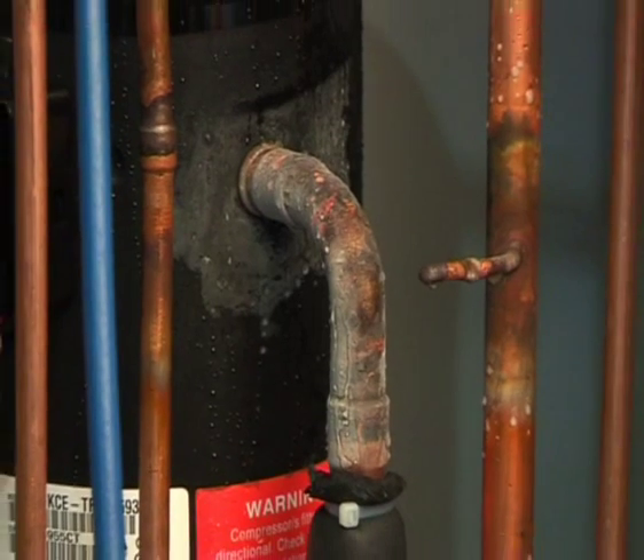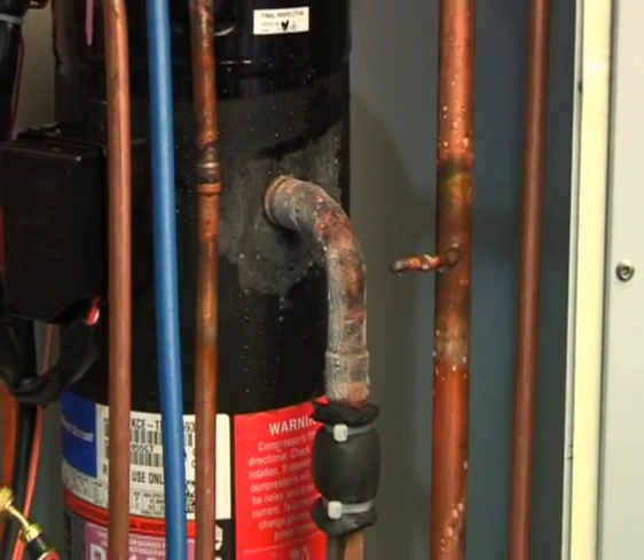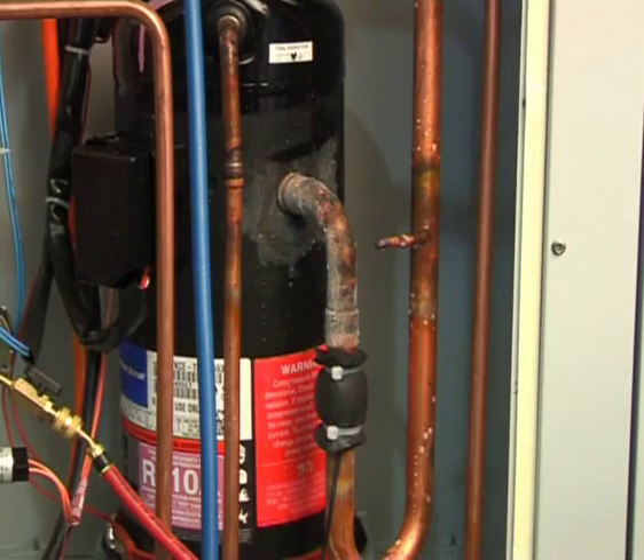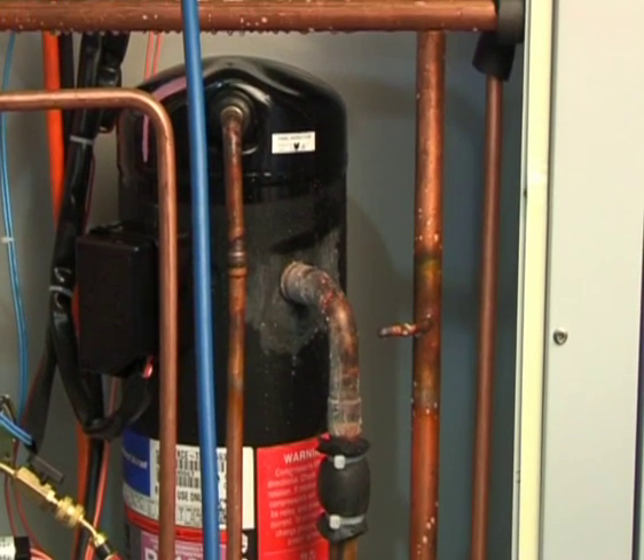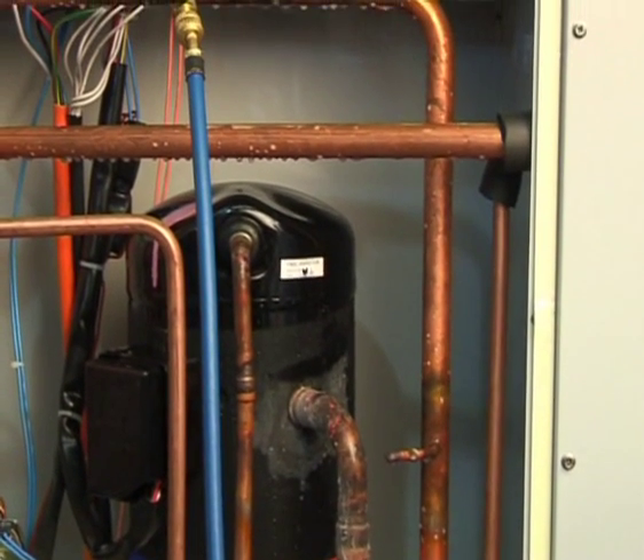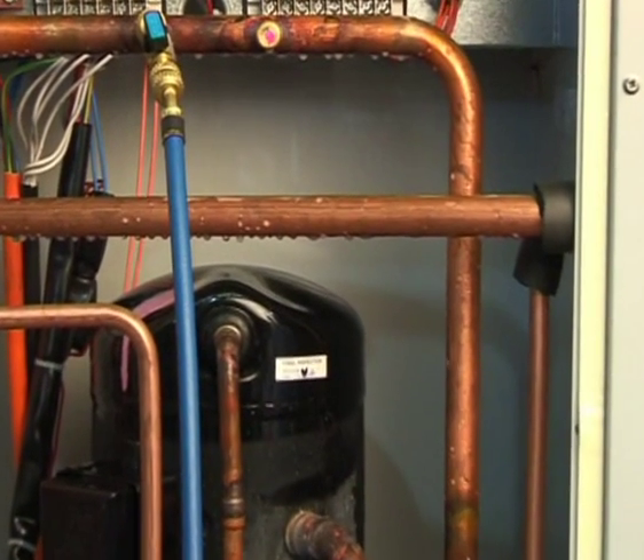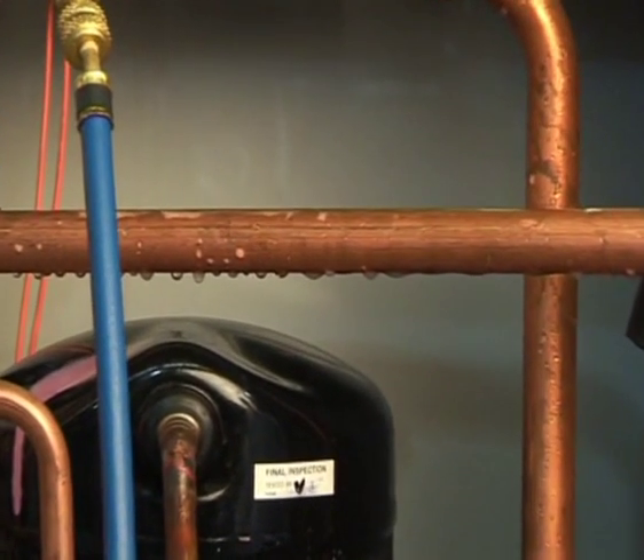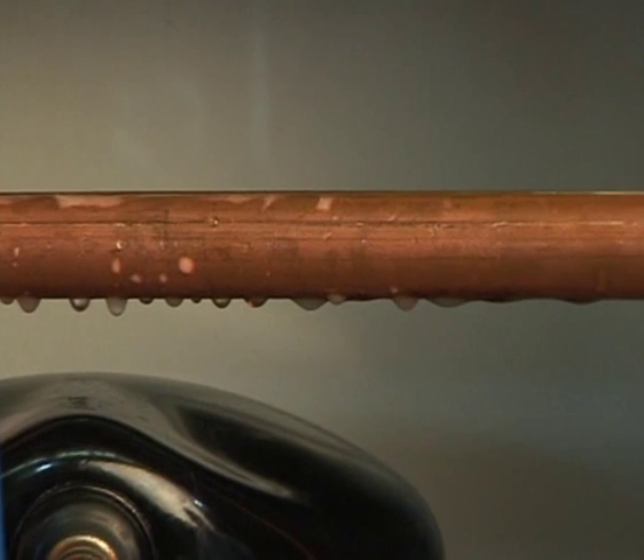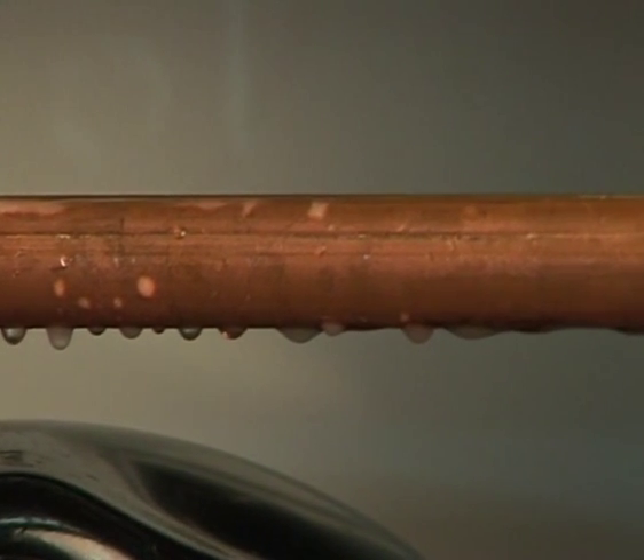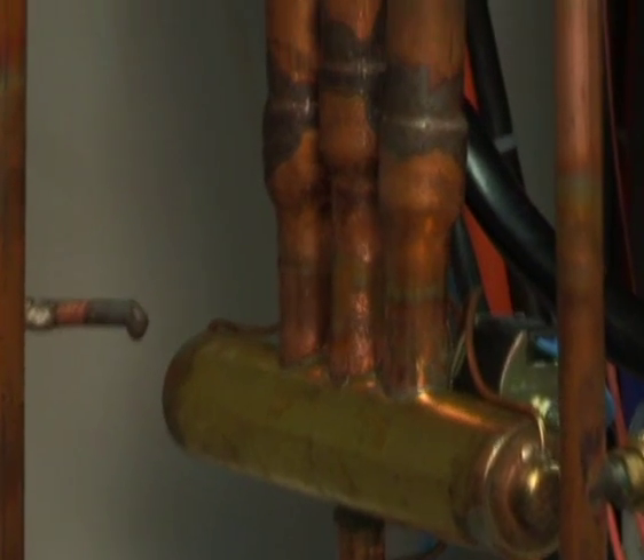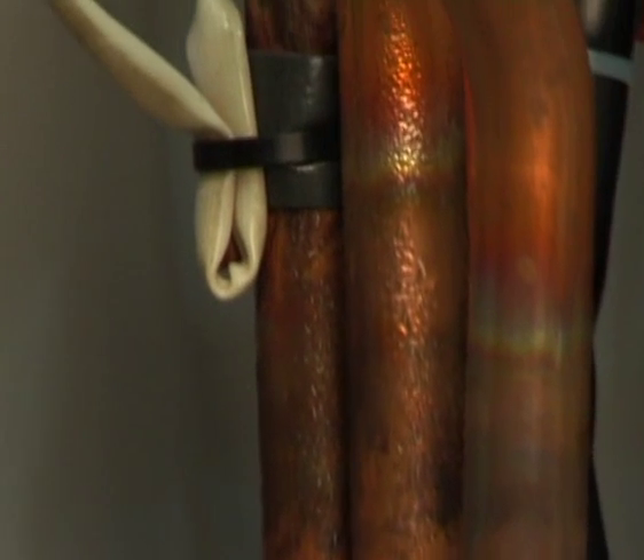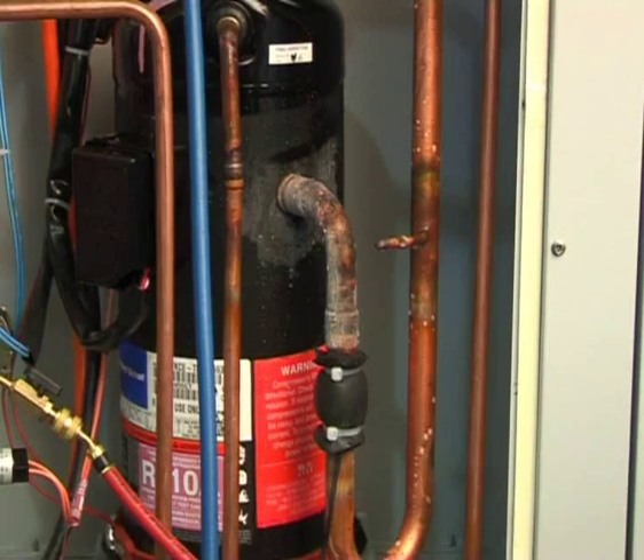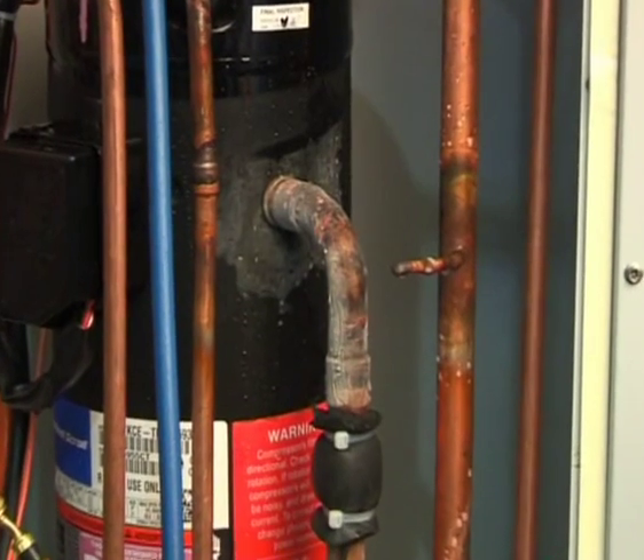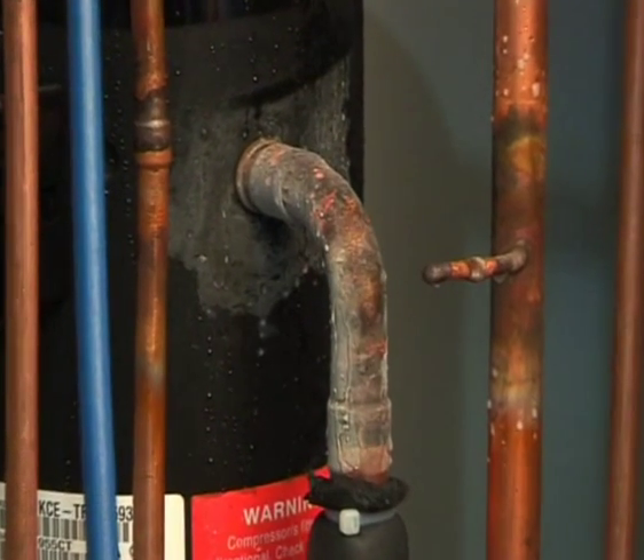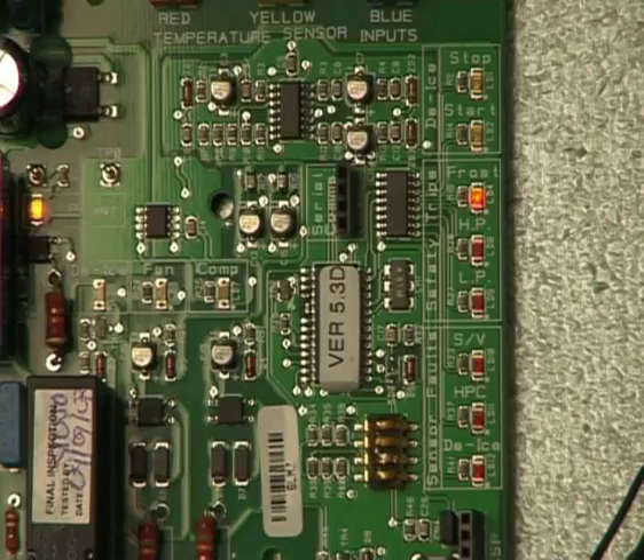Another feature on the cooling cycle is the inclusion of indoor coil ice-up protection. Whether it be dirty or blocked return air filters, low indoor air quantity, belt or motor failure, the Frost Protect feature will shut the compressor down for 15 minutes. The suction temperature is measured by the red service valve sensor. Shutdown will occur when the red service valve sensor detects a temperature of -10 degrees C. Repeated consecutive trips will result in the compressor locking out until power is removed and restored to the unit.